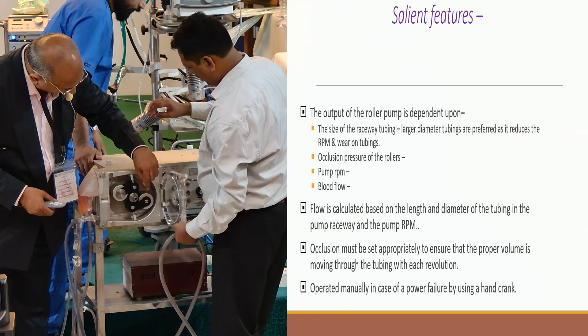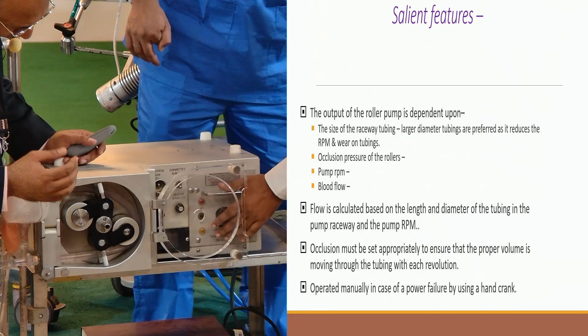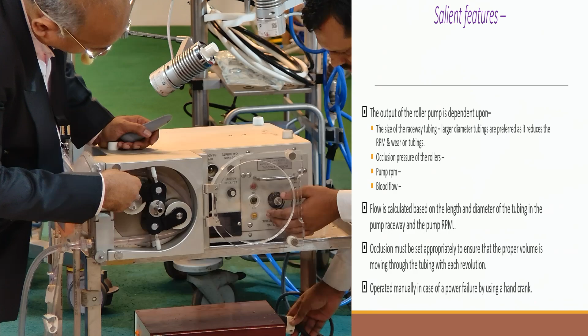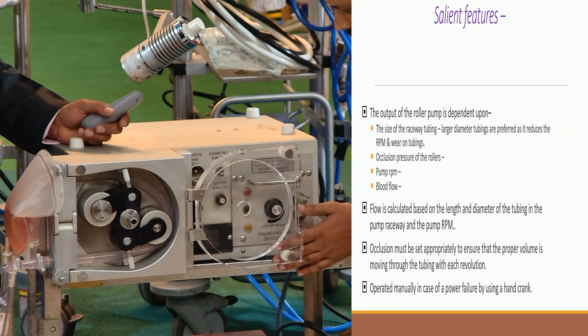Okay. So this is a roller pump, and you have to feed this tube, and this tube you have to adjust this knob so that it does not too tight, at the same time it is not too loose. If it is too loose, this roller pump will move, but the squeezing of tube does not take place. If it is too tight, it will squeeze the tube too much, and then it will cause some plastic release also. So you have to be mindful about it.